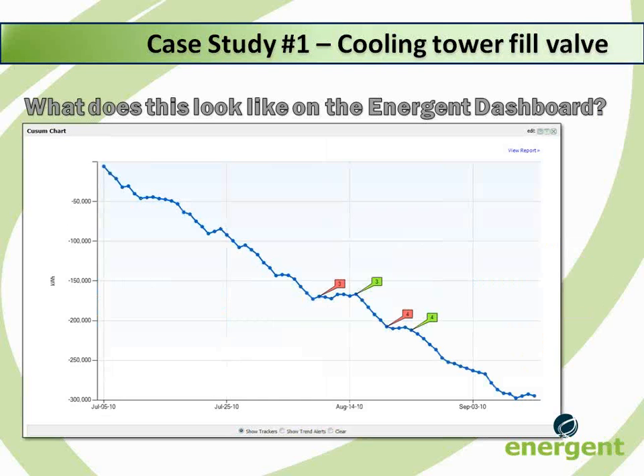This is a CUSUM chart. In energy management, it is a very important summary of the net benefits of energy conservation measures. A CUSUM chart is the cumulative sum of the difference between the predicted consumption, or the model, and the measured consumption, or the actual. A slope that is down and to the right shows a savings trend. A steeper slope indicates more savings, and a flat line indicates that actual consumption is equal to the predicted consumption.